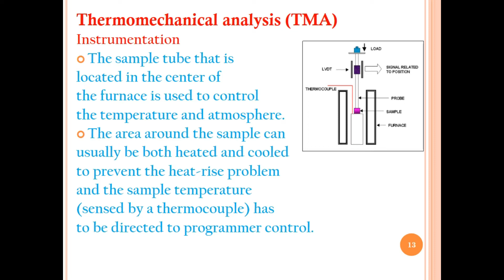The area around the sample can usually be both heated and cooled to prevent heat rise problems in the sample temperature. The furnace in which the sample is placed is temperature controlled. Also, it is connected to the heat sink, meaning it can increase or decrease the temperature, depending upon the material under observation in TMA, after applying the force on the sample by applying a load under different conditions. The temperature sensed by the thermocouple has to be detected for program control.